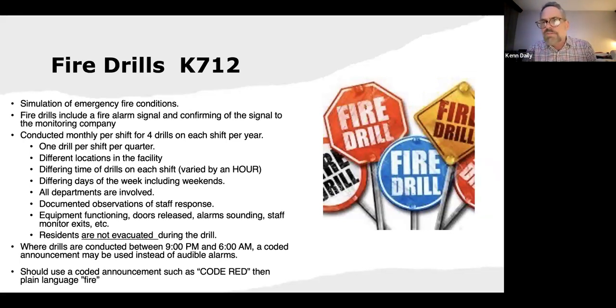Then you do fire drills. We do one per shift, per quarter. So you have 4 fire drills on each shift for a total of 12 fire drills annually. You've got to start them at different locations in your building, and start them at different times of the month. Again, I was looking at a building the other day. Every single fire drill was on the 30th or 31st of the month. Every single fire drill for the past year. And that's not appropriate. They've got to be varied times of the month. So first of the month, second, middle of the month, maybe a Monday, a Saturday, a Tuesday, whatever.